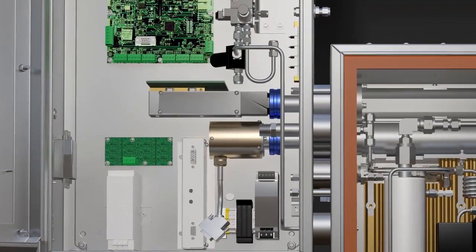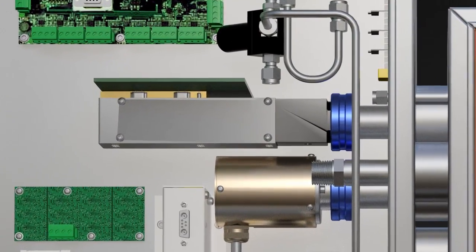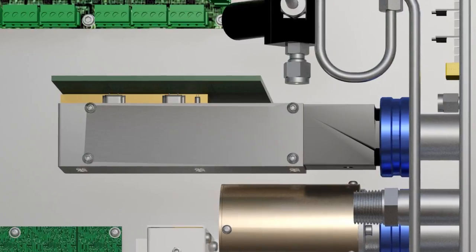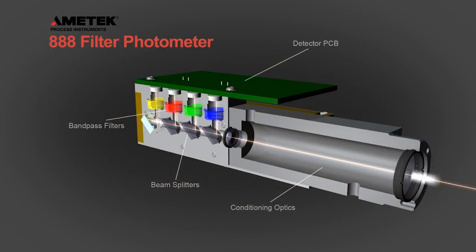The model 888, the successor to the model 880 NSL, uses field-proven and highly reliable UV technology to accurately monitor the hydrogen sulfide and sulfur dioxide concentrations in sulfur recovery tail gas.